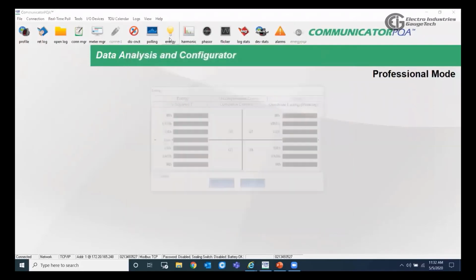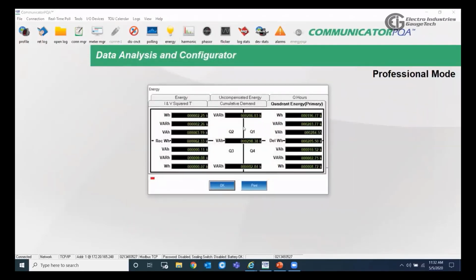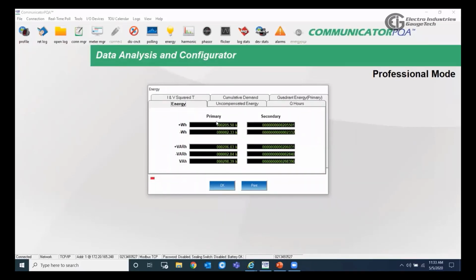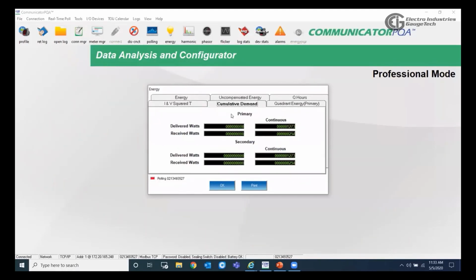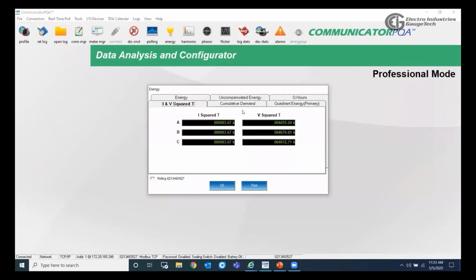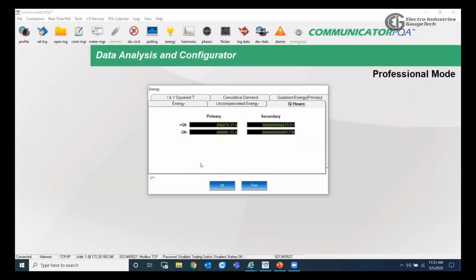The next one would be the energy. This is where we can see all the energy readings. As you can see, we have the delivered watt hour, the received watt hour, the VAR hours, and the VA hours. We also have the option to go to energy here, where we can see the energy on primary and on secondary, which is before multiplying by the CT and PT ratios. And we have also the accumulated demand and the different kinds of energy readings, the I and V squared T, the Q hour, all the energy readings from here.